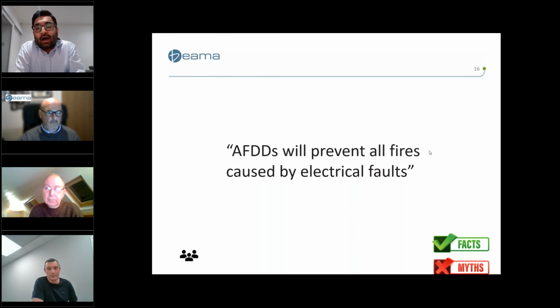And I've had these questions where, can you use arc fault detection products on their own? Well, it depends on the circuit, but where you would need to have short circuit, overload, earth leakage, then no, you would need to use a combination device, or a combination of individual devices to give you that level of protection. So I think you hit the nail on the head when you said it's not a cure-all, it's not a silver bullet. So I agree with you there, Ian.